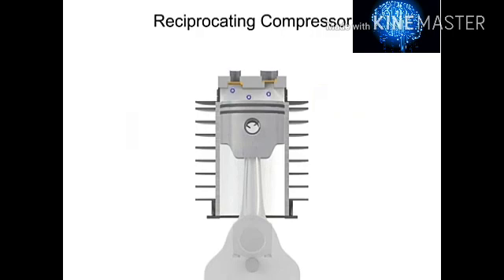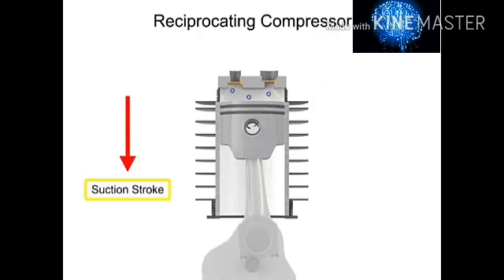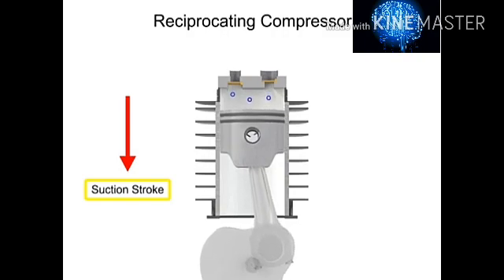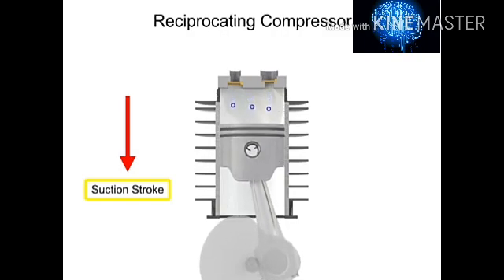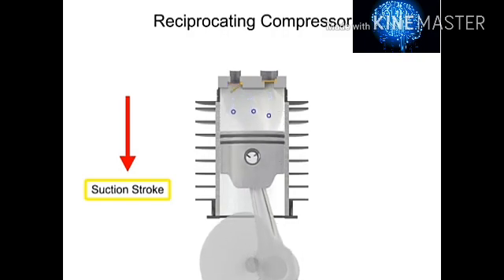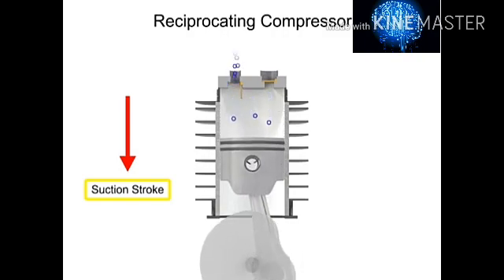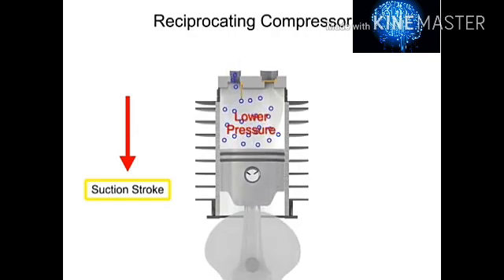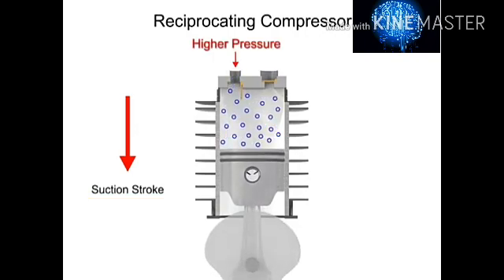As the piston moves downward on its suction stroke, the volume increases within the cylinder. As the volume increases, the pressure within the cylinder becomes lower than the inlet air pressure. This allows the higher pressure outside air to push open the inlet valve and allow more air into the cylinder.